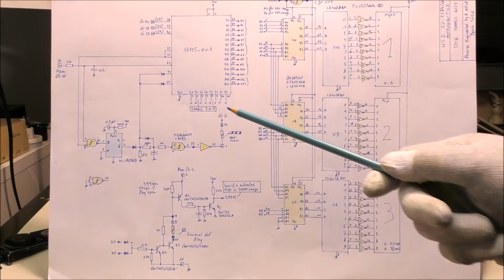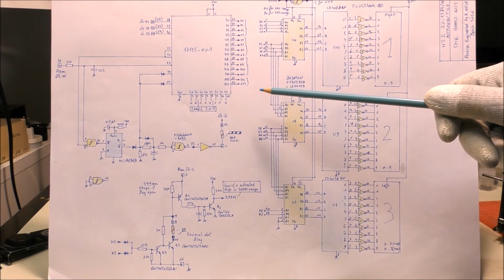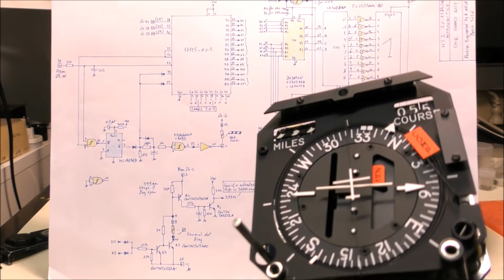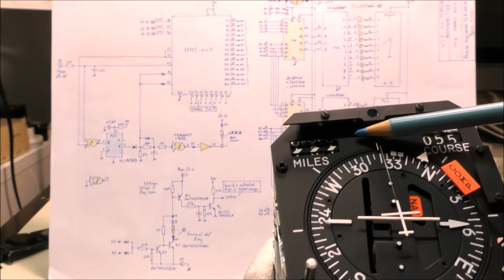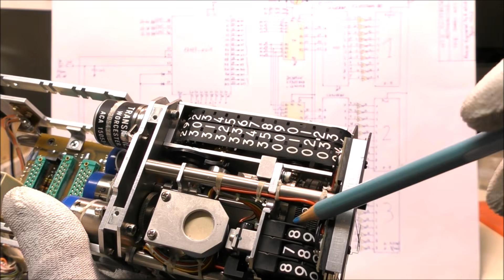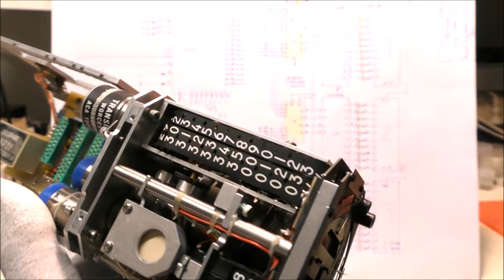If you complement this value, you find 201 corresponding to the DME label. And we have here 4 BCD outputs. The maximum value for DME is 3999, but you can see on that unit we have only 3 digits here. It was impossible to have a 4th indicator because of this cylinder assembly with the gears.